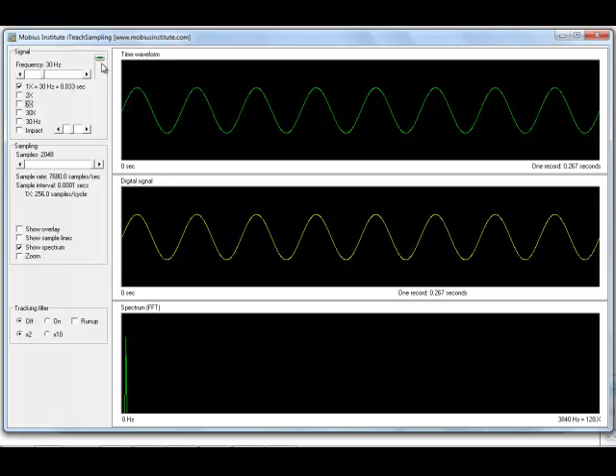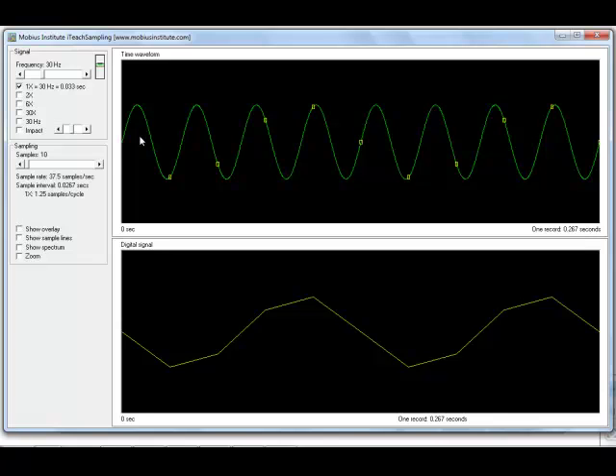But let's explore a little more closely. What we've got is that same analog voltage signal, but we've said to the vibration analyzer that we want to set the sampling rate so that it's quite slow. The number of samples it takes every second is now quite a low number. That means that at this point in time it will digitize the voltage — which is the green value — and keep that value, then digitize it again here and here and here and so on.